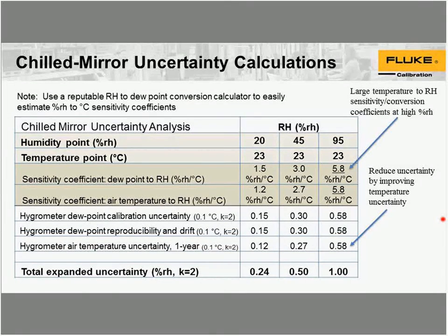Are there any fixed points for measuring or calibrating humidity, like in temperature? Off the top of my head, I don't have one in mind. In some ways, dew point is kind of like a fixed point. It's really a naturally occurring point, and you just have to measure the temperature of it. That's the closest thing that comes to mind.